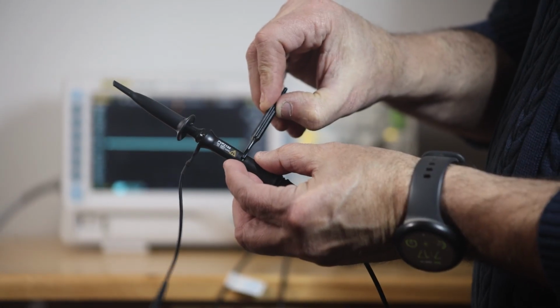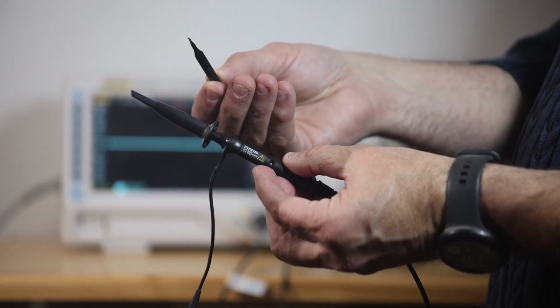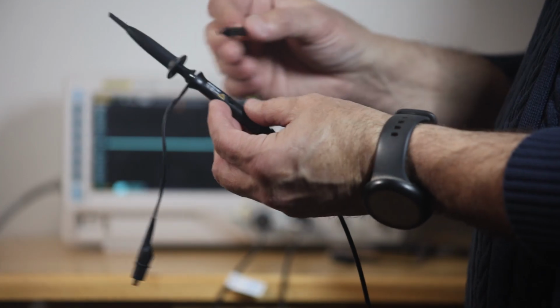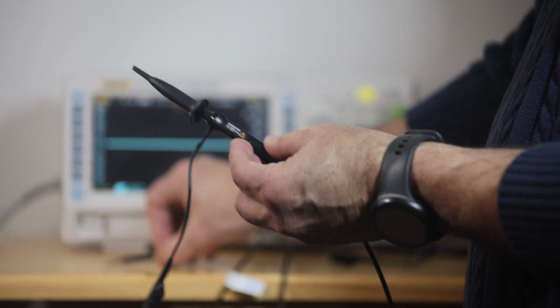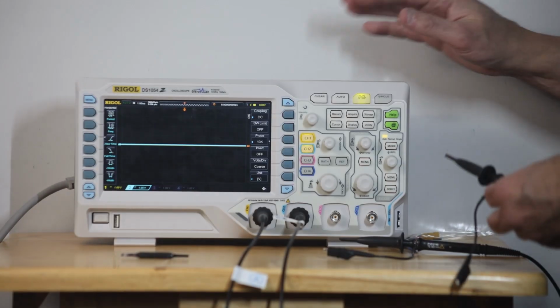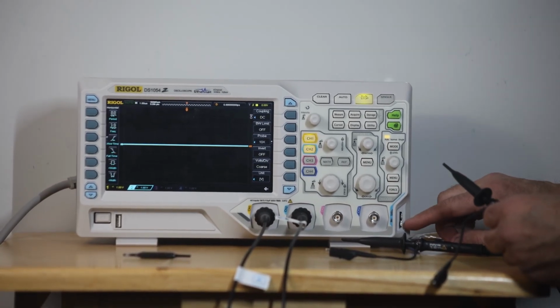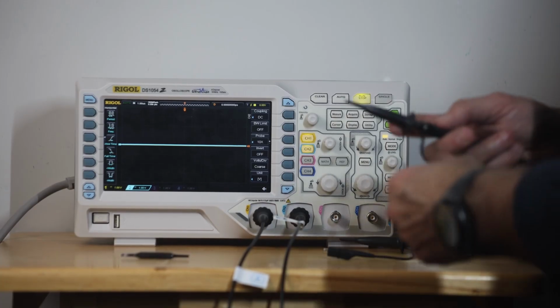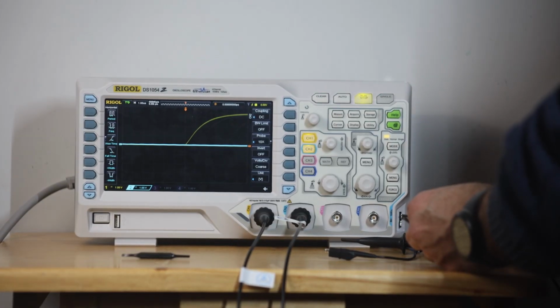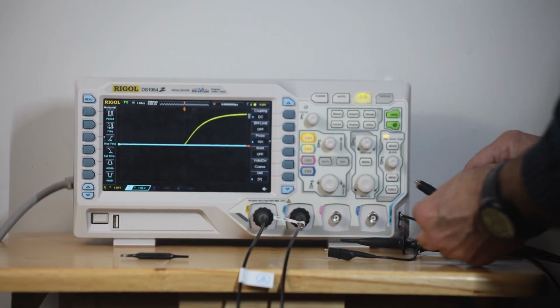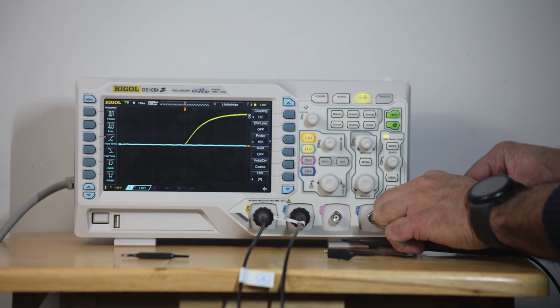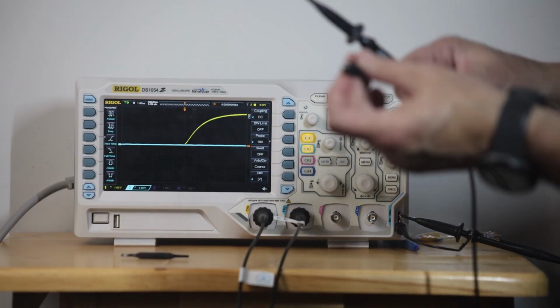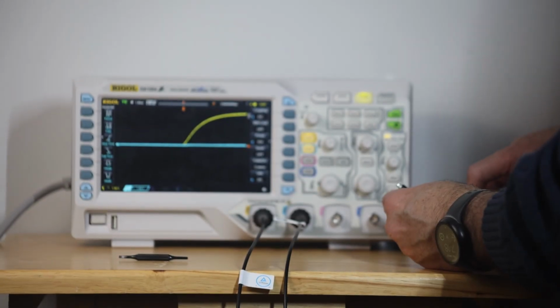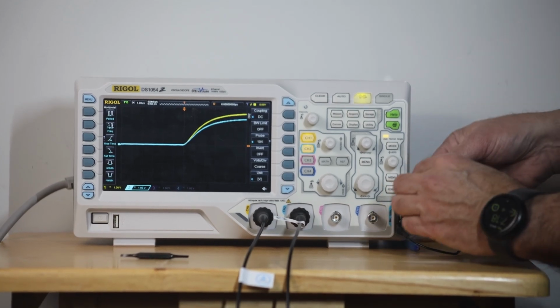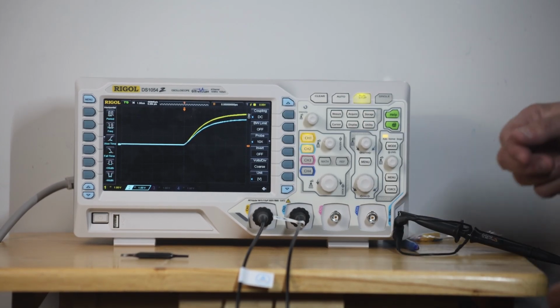On the calibration, there's actually a small little set screw here. And of course, there's a small screwdriver that comes with your oscilloscope. So we're going to be adjusting that set screw, but on the oscilloscope here, it actually has a generator, and there's a top portion and a bottom portion. The top part is the signal generator. So you pull it out, you connect the generator, and you can see there's something happening there. And then you connect the alligator clip on the bottom. Similarly, you take probe B, which is channel 2, connect that up, and then you put the alligator clip on the bottom. So it's starting to get a little bit crowded there.